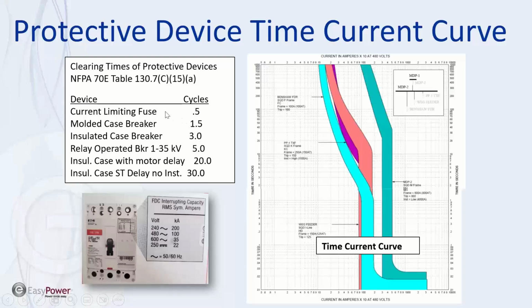So, current limiting fuse: the chart on the left is a note that comes off the 130.7(C)(15)(a) table in NFPA. This note was added in 2009 or 2015. So they finally put in what an average clearing time is for different devices. Current limiting fuses can be a quarter of a cycle up to 2 cycles, depending on the type of fuse that it is. There are different kinds of time current curves for fuses, as well as different time current curves for breakers.